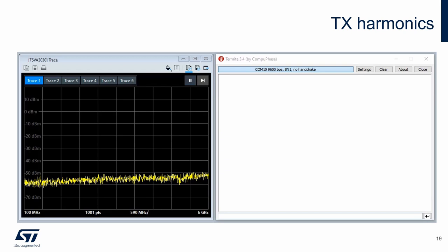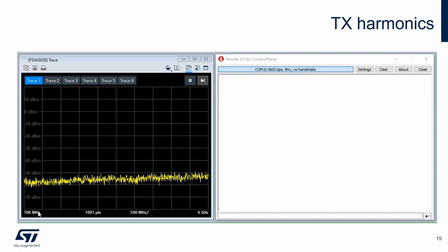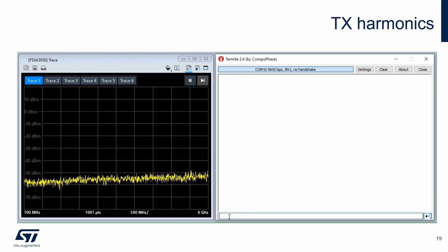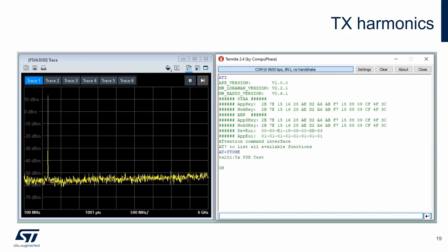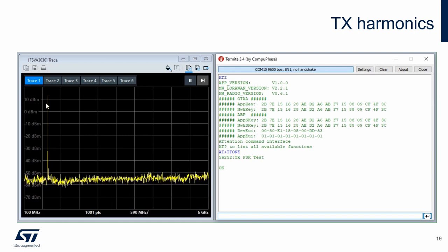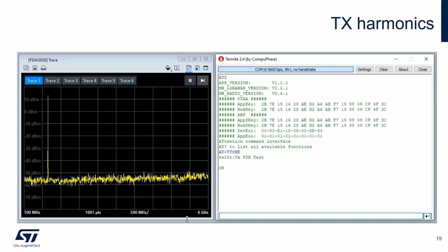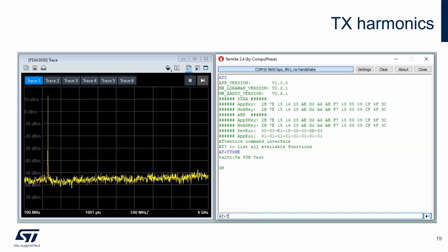Here is a short example of transmitter harmonic measurements. The frequency range of the spectrum analyzer is set from 100 MHz to 6 GHz. First I reset the device by command ATZ, putting it in its default state, and then turn on the carrier at default frequency 868 MHz and 14 dBm. I can see the carrier and no harmonics or spurious signals. If there are any, they may be hidden under the noise floor, which is approximately minus 55 dBm in this case. After the measurement, I turn off the carrier with the T-off command.